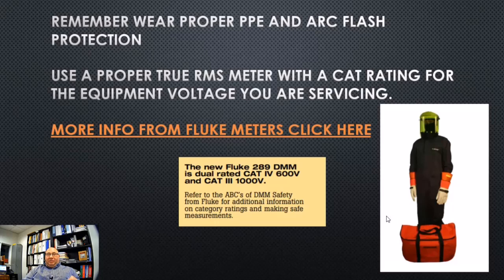So we want to make sure it's true RMS, and we want to make sure that it's either going to be category 3 or category 4, depending on the type of equipment we're servicing. So when I worked at UTC Carrier, we used all category 4, but we also worked on bigger starters and bigger motors.